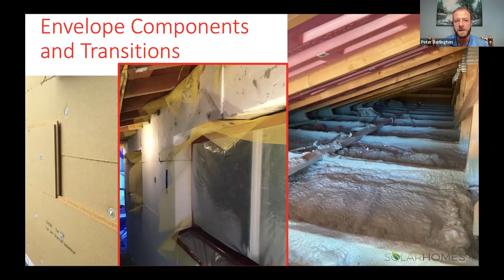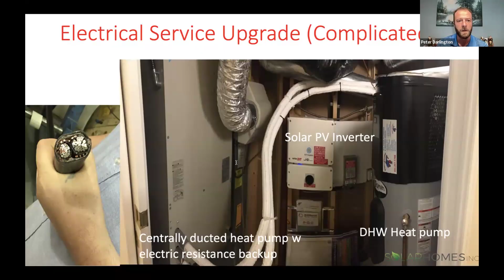Typically, a 100 amp service is available on most homes. Switching heating systems over to electricity from methane or natural gas adds a significant amount of load to an existing service. In some spots, a service upgrade is possible and simple. In other buildings, some type of load share may need to be used. There have been some new items come to market on the load share side in the last couple of years that make this a little bit easier, but you definitely want to have an electrical plan going in.